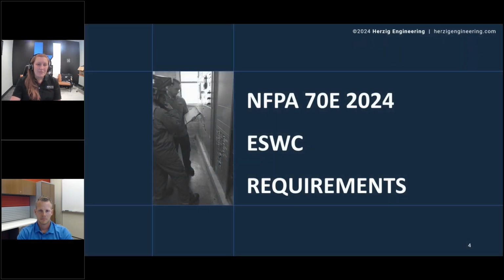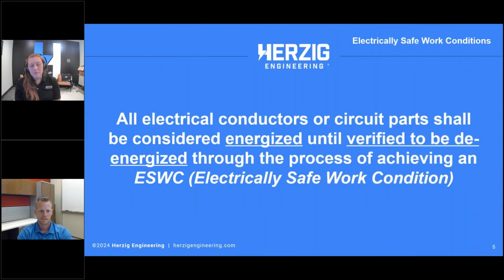All right, so let's dive into those requirements. How do we get an electrically safe work condition? Well, what's the purpose of that? Frankly, all electrical conductors or circuit parts are considered energized until verified to be de-energized through the process of achieving an electrically safe work condition.